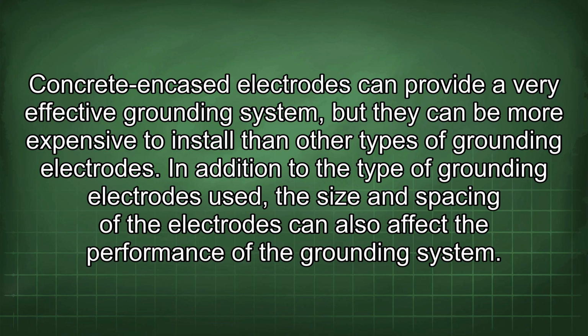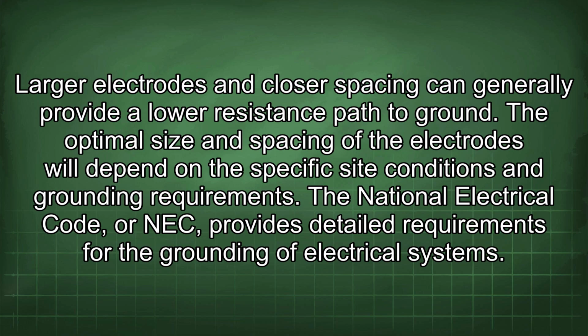In addition to the type of grounding electrodes used, the size and spacing of the electrodes can also affect the performance of the grounding system. Larger electrodes and closer spacing can generally provide a lower resistance path to ground. The optimal size and spacing of the electrodes will depend on the specific site conditions and grounding requirements.